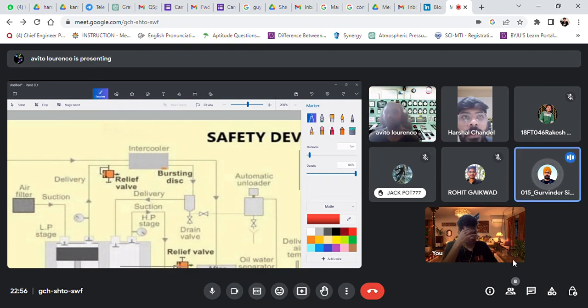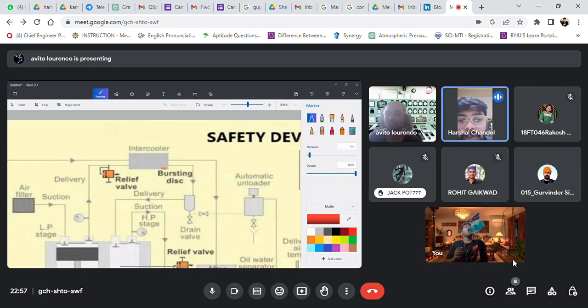I think it must be something related to pressure on the water side of the intercooler. Yeah, on the second compressor also you will see the air is leaking, so the pressure won't develop. Hopefully Sandy can give us the exact understanding of what exactly is going on. Let's leave that.